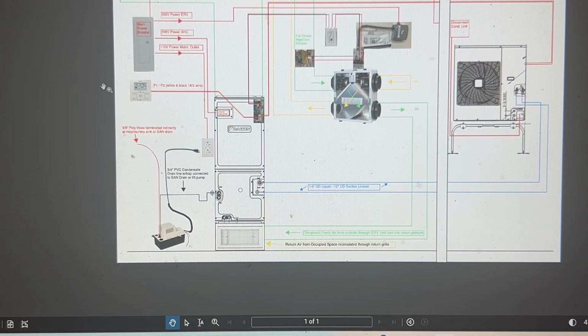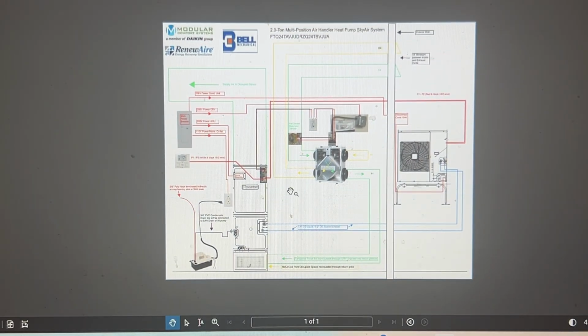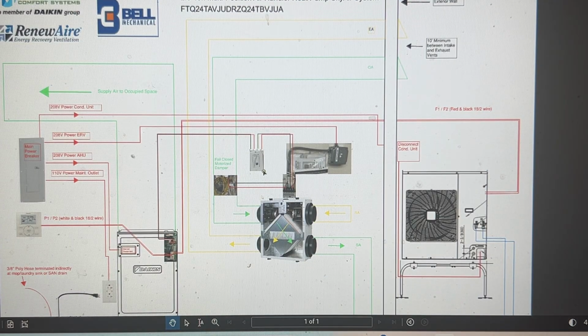So let's dive in a little bit. We'll start with the ductwork portion. On our energy recovery ventilator, they put this in here to try to temper the outside air that comes in as makeup air. So we have to have air turnover every so often in the townhome. When they bring in that outside air, they want to temper it with some of the existing air within the unit, so that the heat pump doesn't work as hard on that fresh air to get it climate controlled before it pushes it up to the floors.